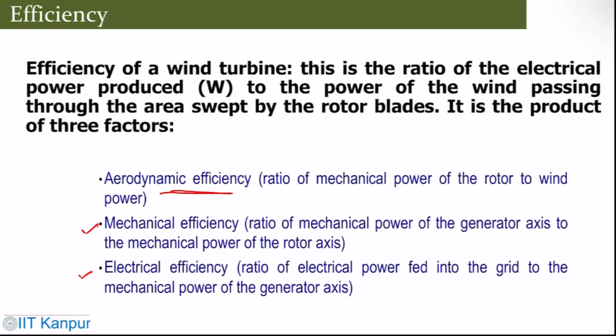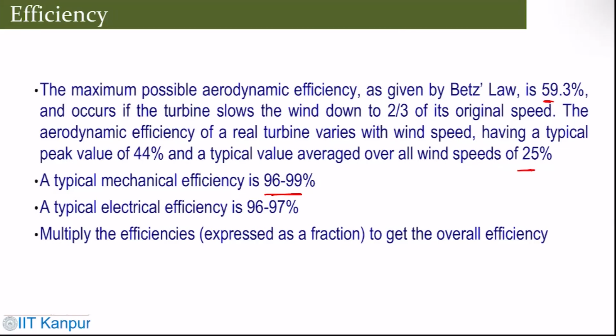The maximum possible aerodynamic efficiency is given by the Betz law or Betz limit, which is 59.3%, which occurs when the turbine slows the wind to 2/3 of its original speed. Aerodynamic efficiency of a real turbine varies with wind speed, having a typical peak value of 44% and average values of 25%. Typically the mechanical efficiency is on the order of 96 to 99%, and electrical efficiency is on the order of 96 to 97%. Then multiply these efficiencies to get the overall efficiency.